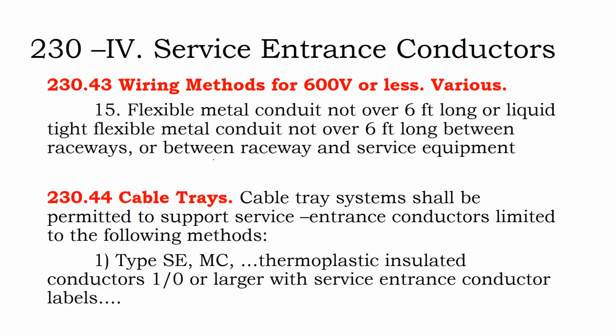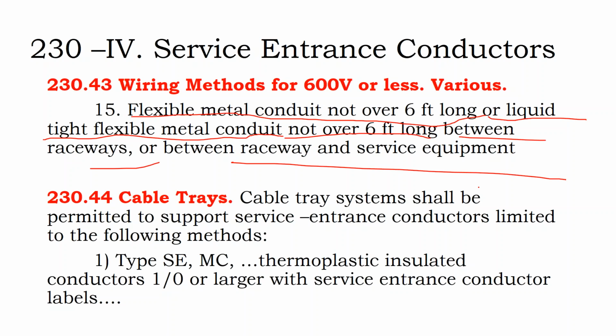Let's see, wiring methods for 600 volts or less. We have flexible metal conduit, not over 6 feet long, or a different kind of metal conduit called liquid tight metal conduit. Flex metal is exposed metal. Liquid tight has a PVC coating over the top of it. Not over 6 feet long between raceways, or raceways and service equipment. We were doing one job where we're using flex conduit to come into the rooftop through the roof cap. The only way we can make that conduit bend work in an easy manner is to take flex conduit up on the rooftop and then route it through the roof cap. It's harder than it sounds. We had to use a 45-degree fitting just to get the conduit going in the right direction.